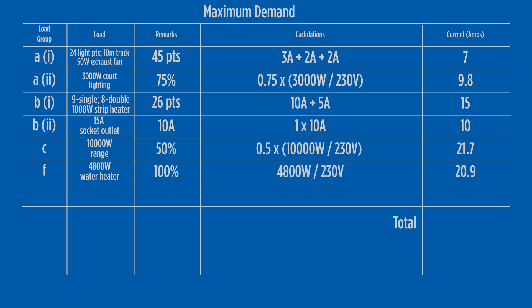We now add all the loads allocated to each load group together. This value is the calculated maximum demand of the installation. The maximum demand in this installation is 84.4 amps, and the mains cable will be selected based on this value.